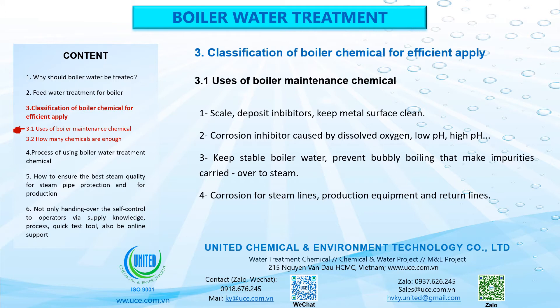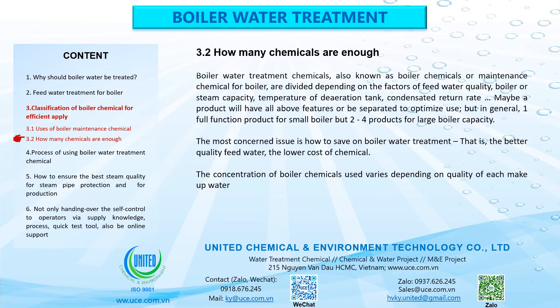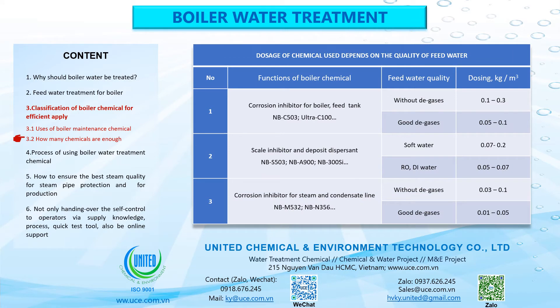3. Classification of boiler chemicals for efficient application. 3.2 How many chemicals are enough? Boiler water treatment chemicals, also known as boiler chemicals or maintenance chemicals for boiler, are divided depending on factors such as feed water quality, boiler or steam capacity, temperature of deaeration tank, and condensate return rate. A single product may have all the above features, or they may be separated to optimize use — in general, one full-function product for small boilers but 2–4 products for large boiler capacity. The most important consideration is how to save on boiler water treatment: the better the feed water quality, the lower the chemical cost. The concentration of boiler chemicals used varies depending on the quality of each makeup water.